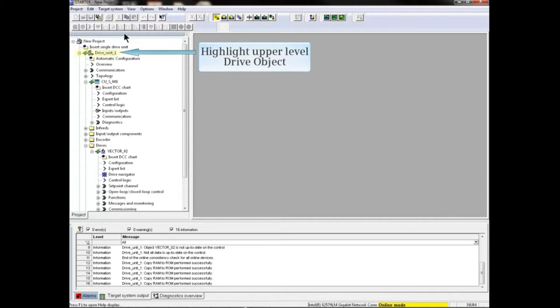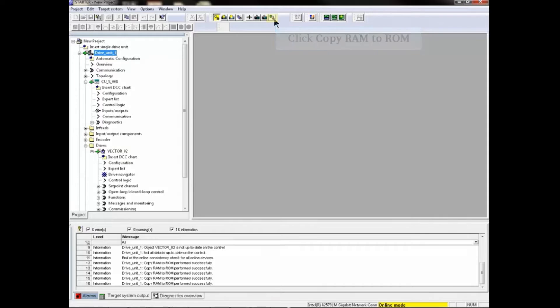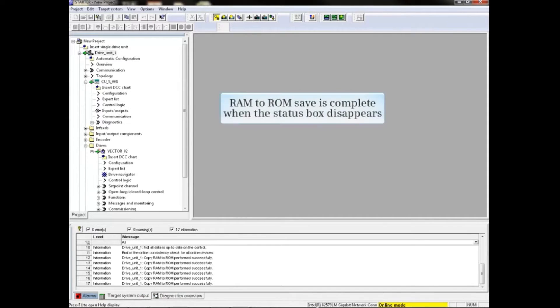Once again, you start by highlighting the upper level drive object. You then click the Copy RAM to ROM icon from the menu bar. The RAM to ROM save is performed and a status box appears. When the status box disappears, the RAM to ROM save is complete.